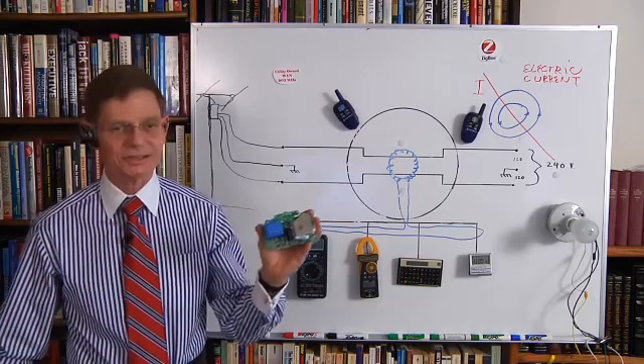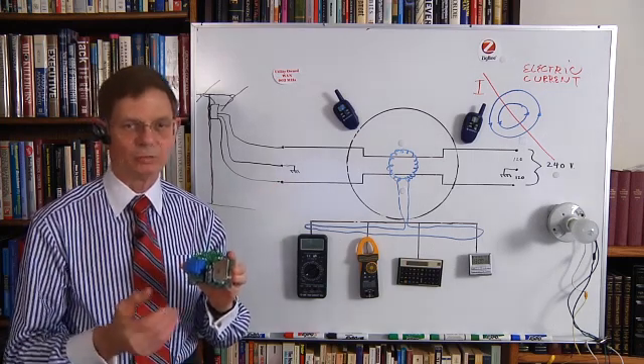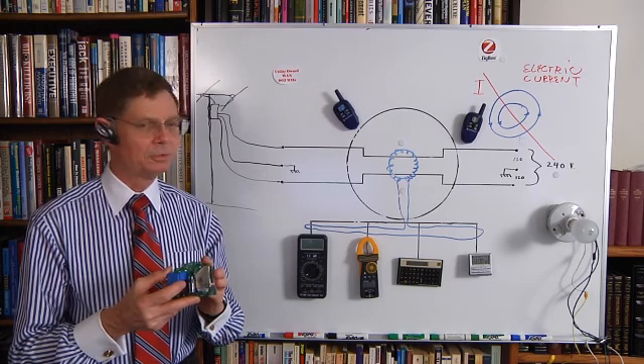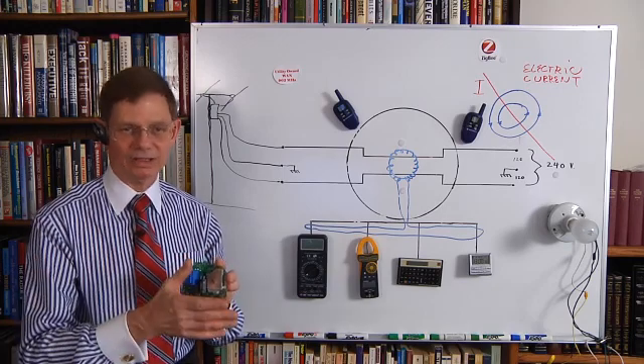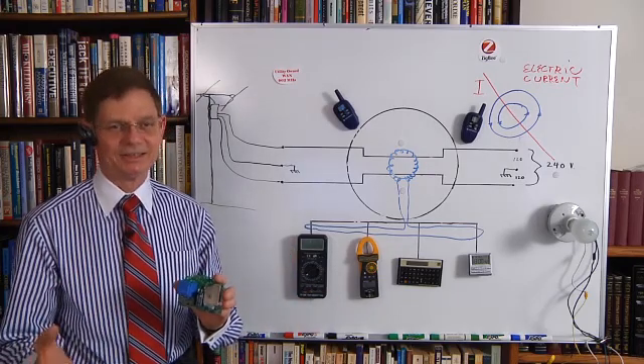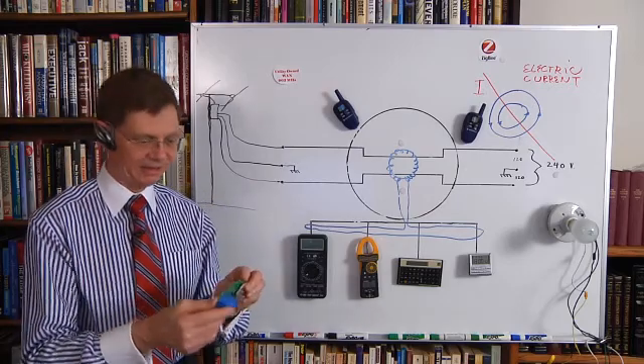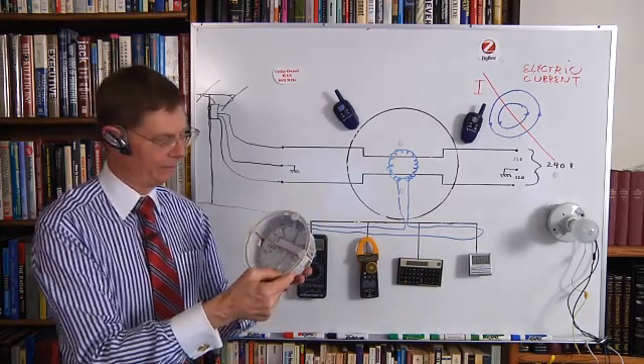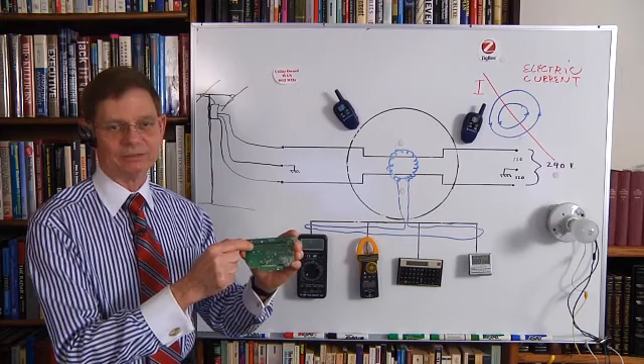The meter electronics is located on this circuit board, and it operates using very low voltages, 12 volts and 5 volts, which is produced from a switch mode power supply. Switch mode power supplies are used by virtually every electronic device in your home connected to 120 volts. Things such as your iPhone power charger, television sets, electric clocks, all of these devices use switch mode power supplies. The electronics is connected to the liquid crystal display located inside the meter's clamshell using a series of electronic connecting points, or what we call pads, on the rear of the circuit board.